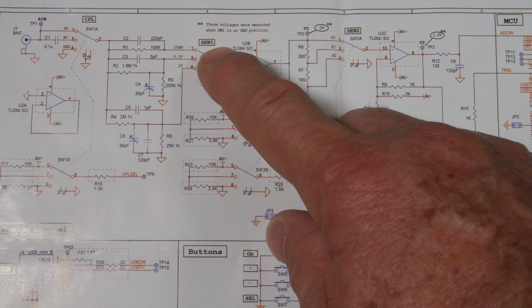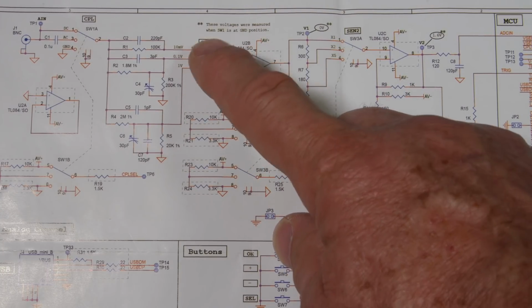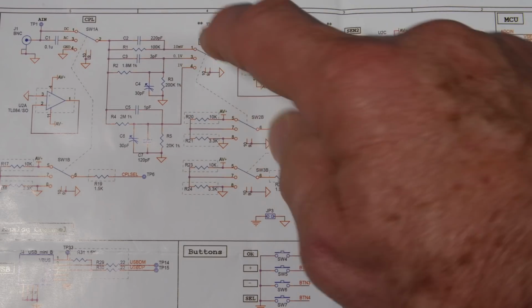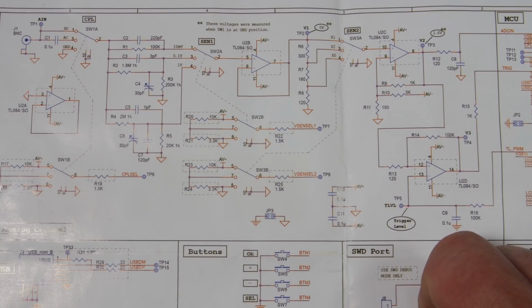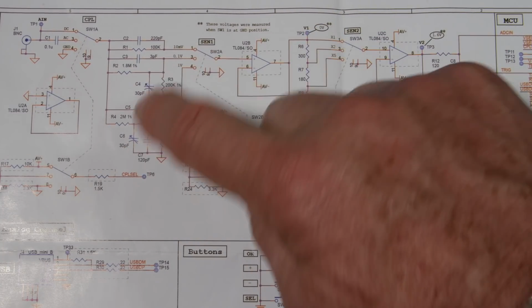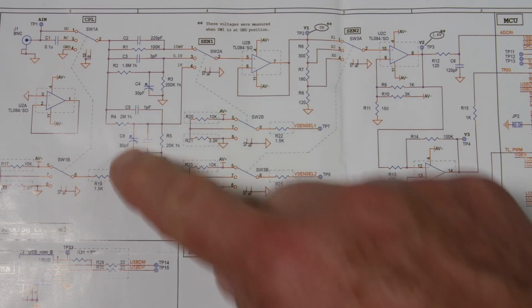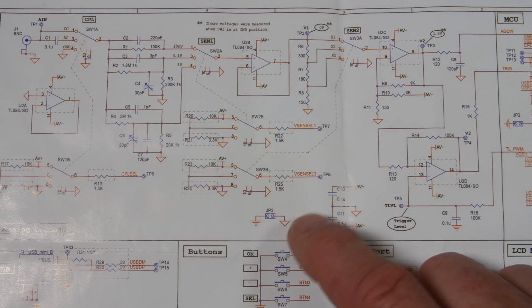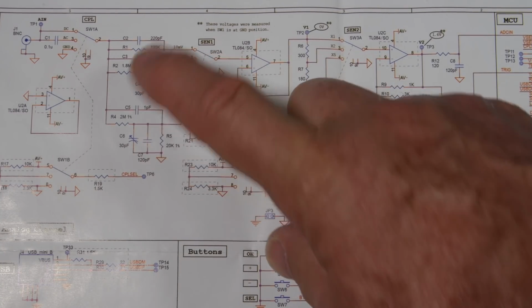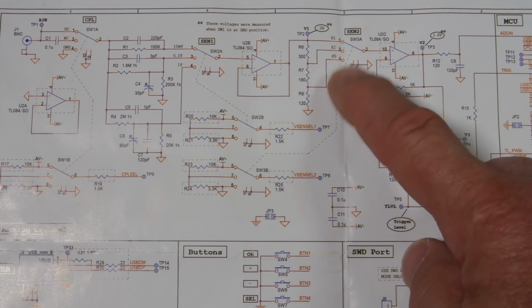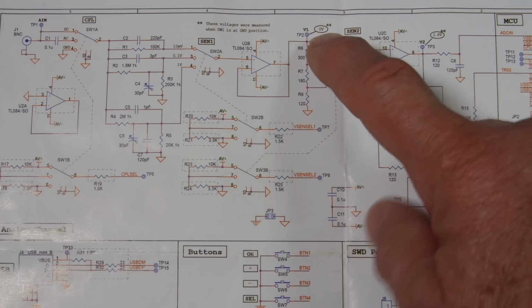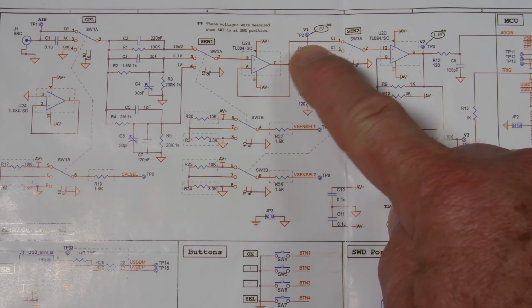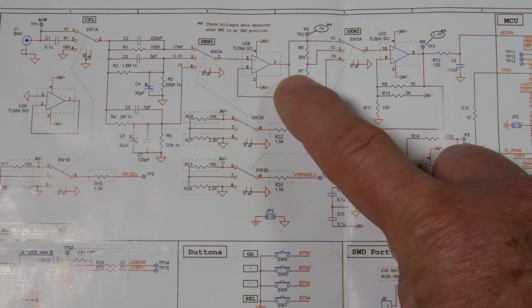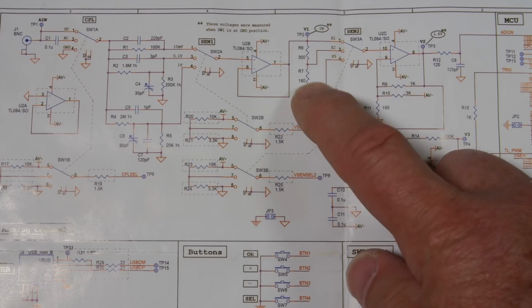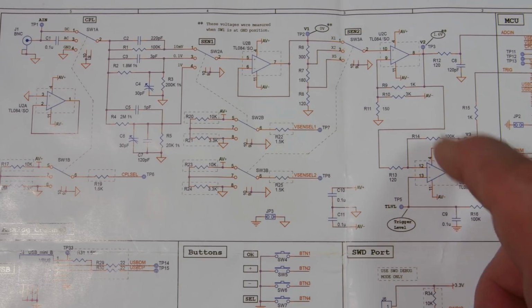Okay, so then the next thing is the Sense 1 range, and you can go from 10 millivolt, 0.1, and 1 volt, and they show the actual circuits that it's going through for each one of those. Oh, and here's the C4, C6 trim capacitors for the calibration. Okay. So you can see we have to be at 0.1 or 1 volt to use those, and the 10 millivolt doesn't have one, just comes straight through. Sense 2 has 3 positions. They call it X1, X2, and X5, and that's a voltage divider. So signal comes in through the top one that goes right through for X1, or it divides it down to X2, or divides it again for X5. Then goes to another op amp.